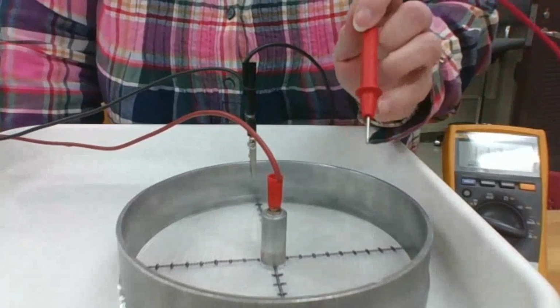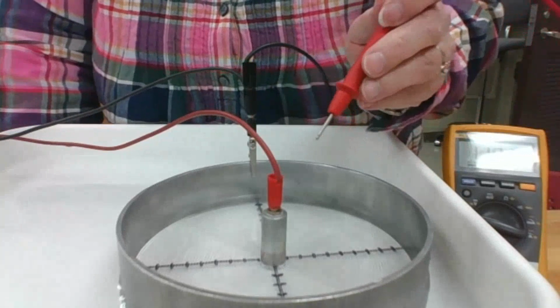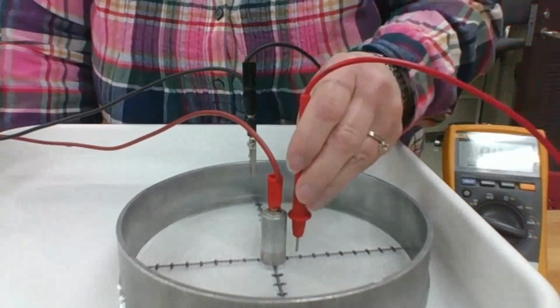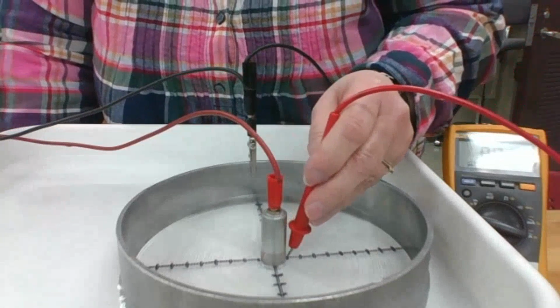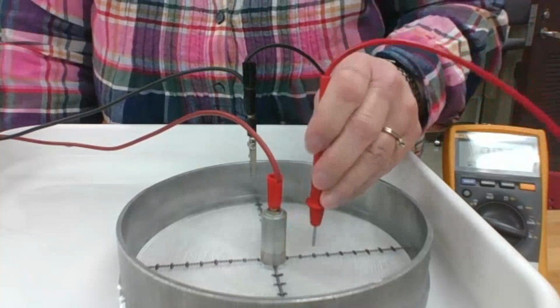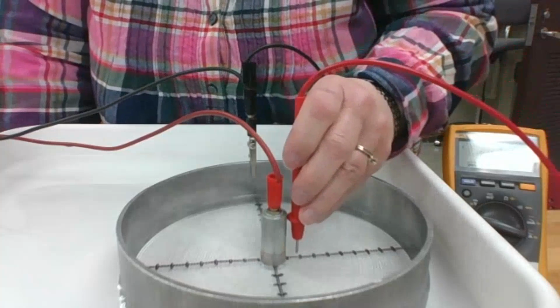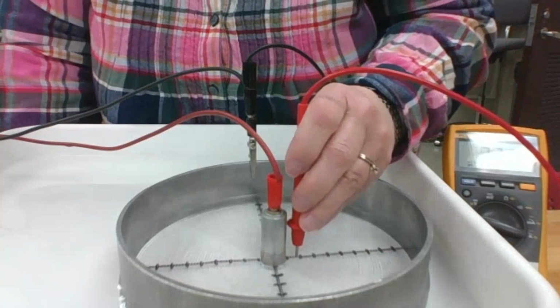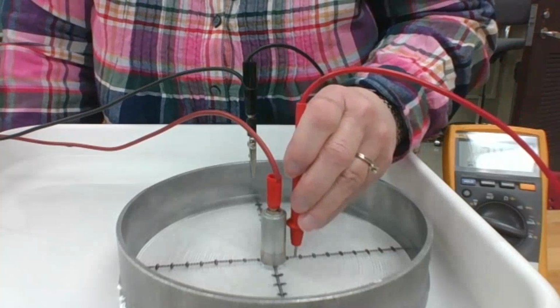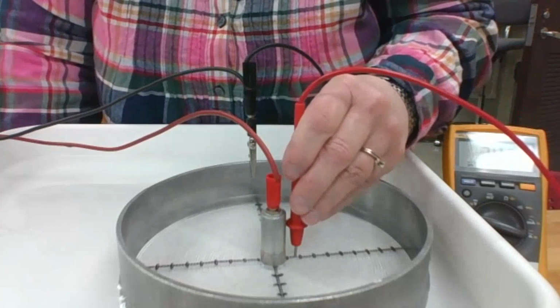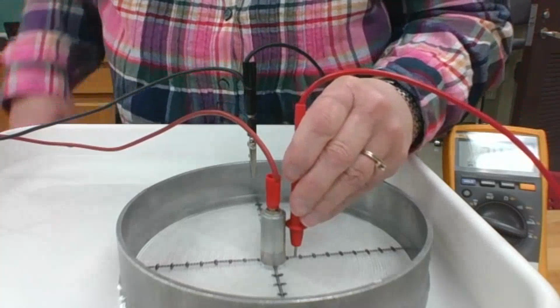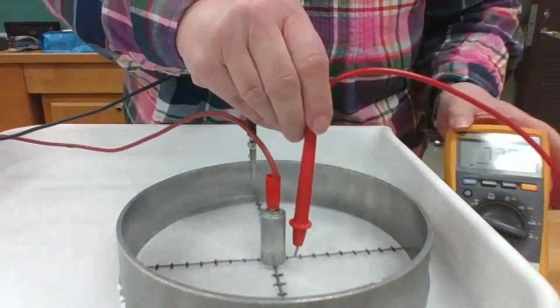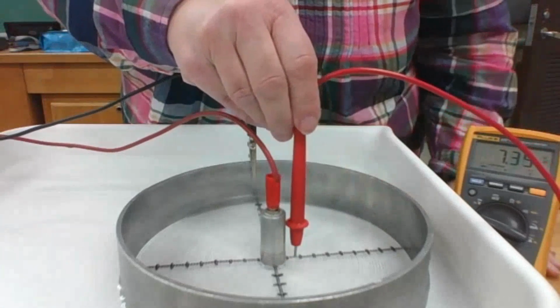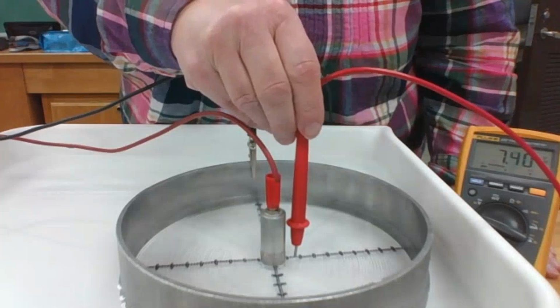You'll note that the probe has a ring on it. It's going to prevent us from getting all the way into the 10 millimeter mark. Why? Because the probe must be kept perpendicular to the surface of the water. So I'm going to start here. This is 16 millimeters from the center, and the recording is 7.40.